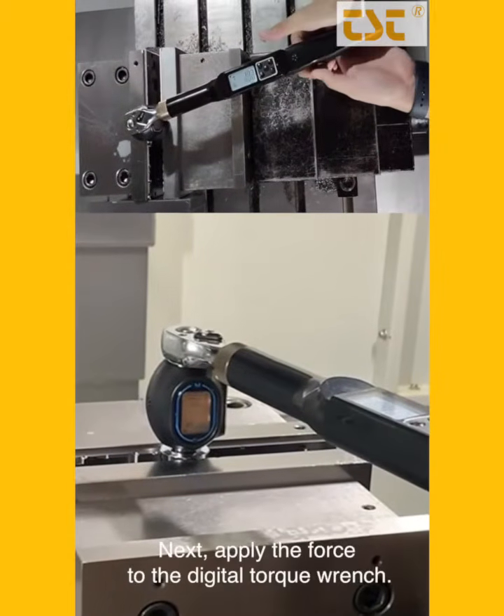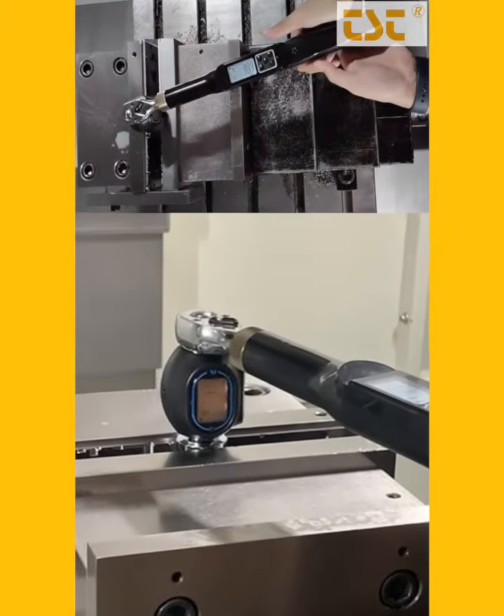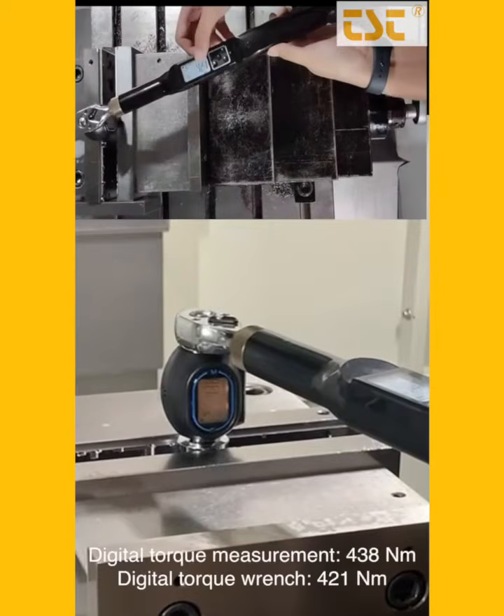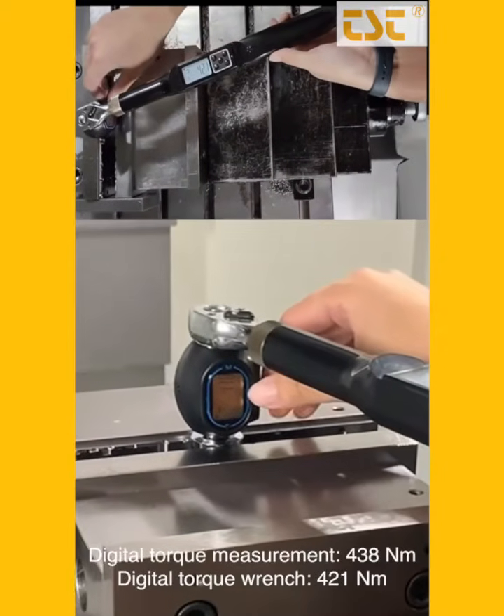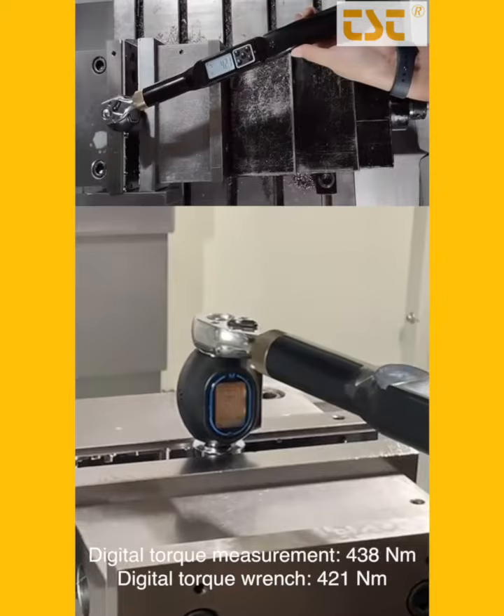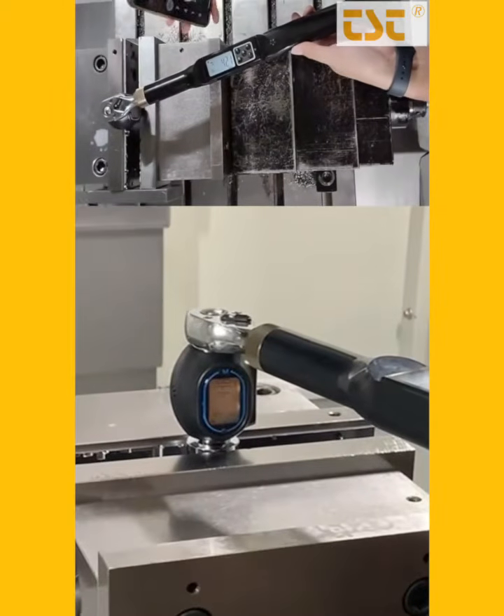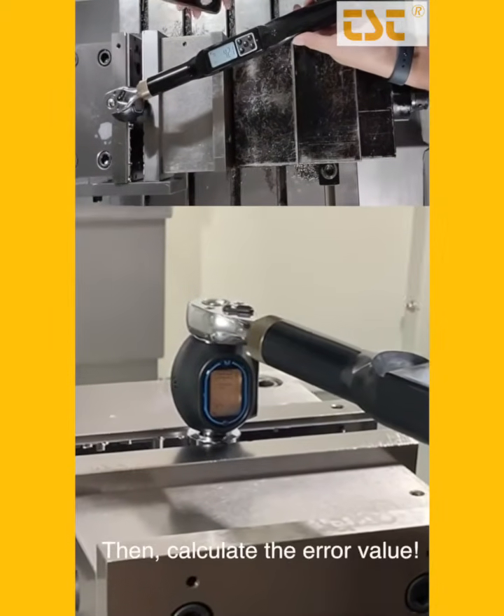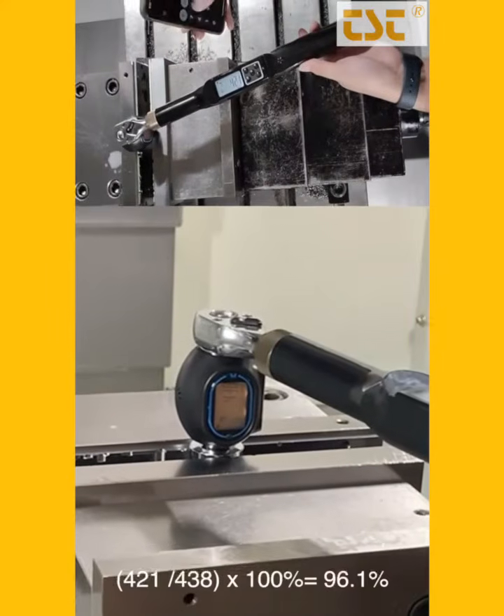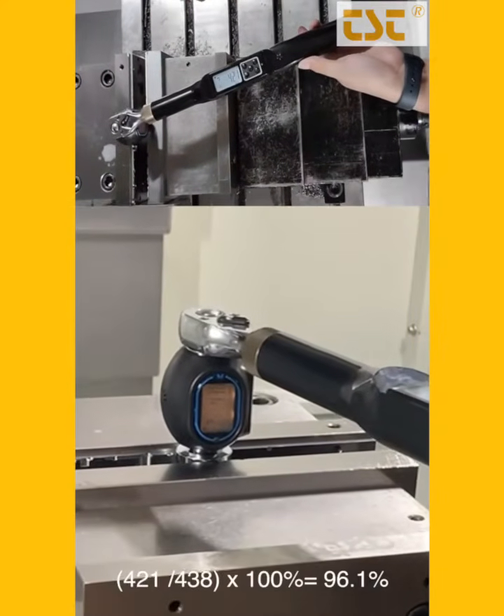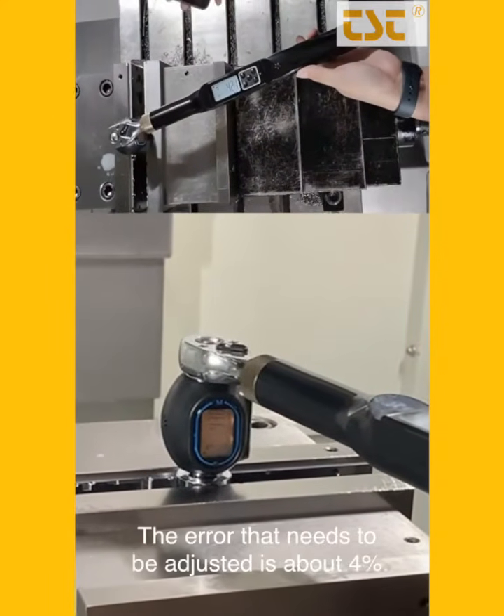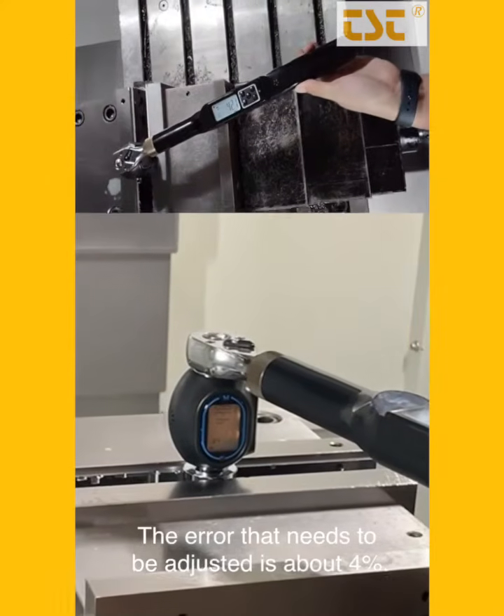Next, apply the force to the digital torque wrench. Digital torque measurement: 438 Nm, digital torque wrench, 421 Nm. Then, calculate the error value. The error that needs to be adjusted is about 4%.